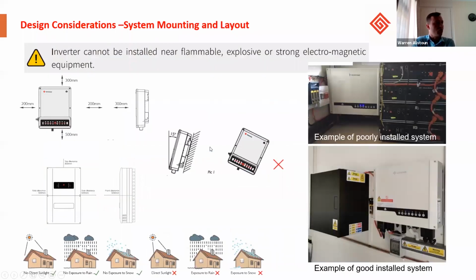Moving on from the Easy Designer tool, we need to consider the system mounting and layouts. So very important to get this aspect right. On the right-hand side here, I've got an example of a poorly installed system, and at the bottom, a well-installed system. So the system above here, should the client need support on the product, cannot get into the SEMS portal, we require a serial number, they will not be able to get to the serial number. As well, there's not enough space left to right, causing heating issues and causing derating of the product. Again, underneath, you cannot service the product.